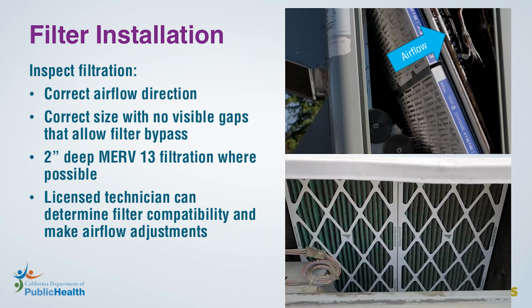Additionally, ensure that the filter sizes are correct and that they are installed correctly in the filter racks so that no visible gaps are present. Any air that goes through gaps does not get filtered. This is called filter bypass.